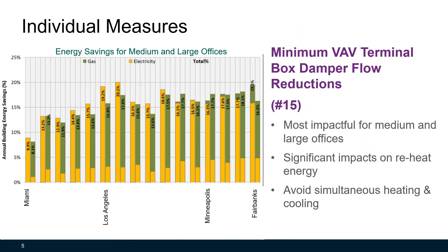This chart shows energy savings for medium and large offices for a minimum VAV terminal box damper flow reduction strategy. The annual building energy savings on average is almost 15 to 20 percent, which is very significant. This strategy is most impactful for medium and large offices and has a significant impact on reheat energy.